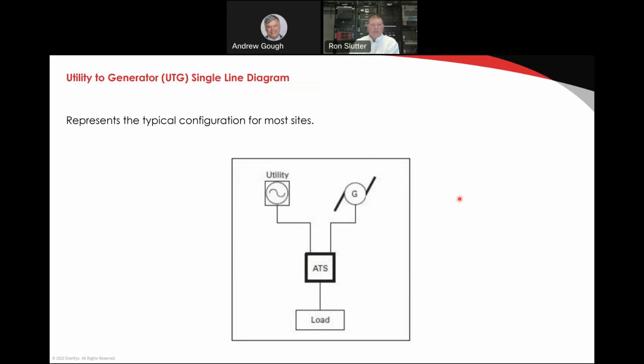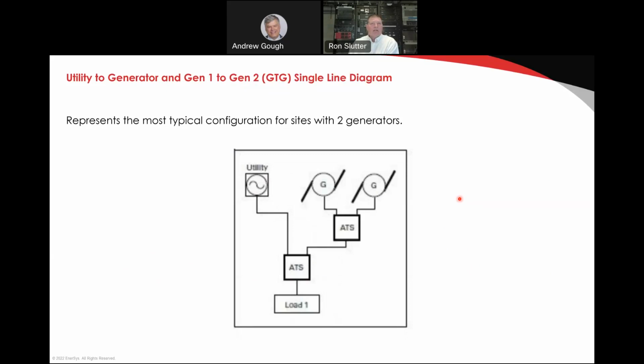Very straightforward, very simple. As we move into more complex sites and more reliability is required, some sites have a single utility service and will have two generators, each generator connected to a separate ATS, automatic transfer switch, and then connected on the output of that on the load side to the utility to gen ATS. So if I were to give you a generic description of the ATS connected to utility, that would be a utility to generator connection. We call that a U to G for short, for typical short conversations. And the ATS connected to the two generators, we call a G to G, obviously gen to gen ATS. So just to keep our acronyms short and sweet when we're doing our discussion.